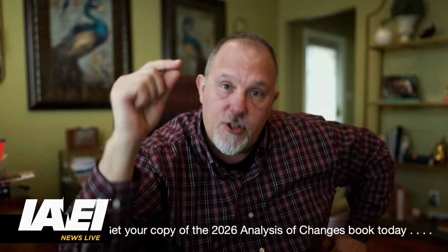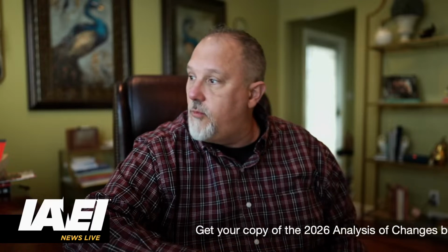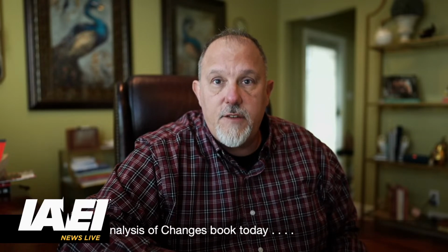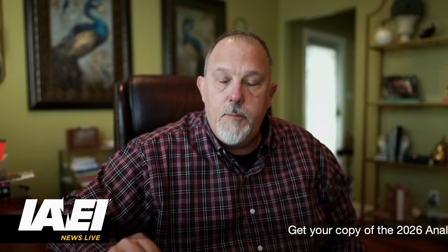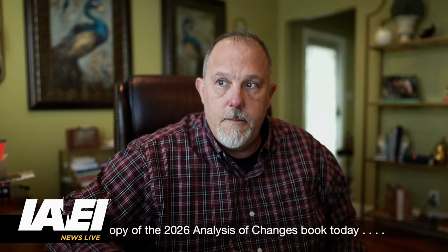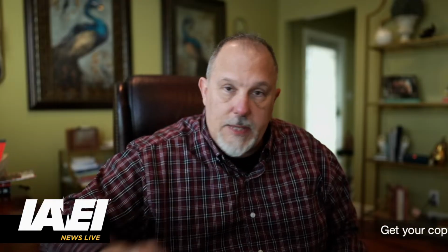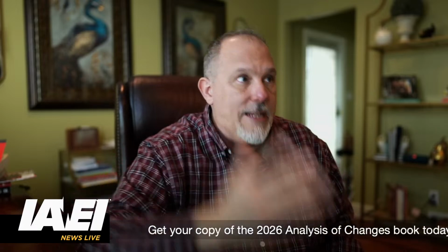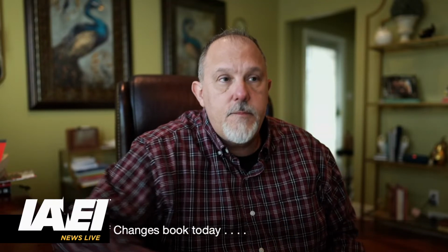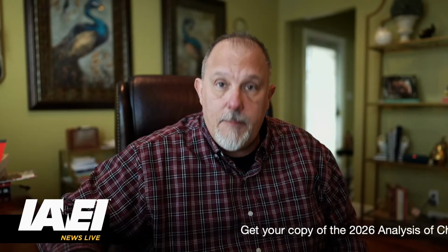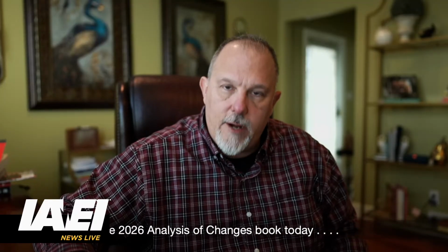Article 625 handles electric vehicle charging equipment. I've heard some people say that in 625 they were going to make modifications to provide some relief on hardwired electric vehicle charging equipment. But what 625 did got appealed, and they removed everything. So now you're left with what was in the previous edition of the code, the 2023 code, which just says electric vehicle charging equipment that's cord and plug connected has to be GFCI protected. It doesn't say anything about hardwired. So I've heard some people say hardwired is not required to be GFCI protected, and that is not correct.